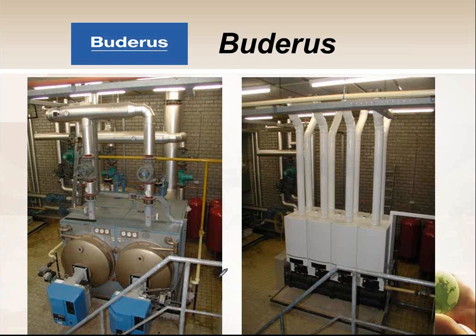Dan's asking if you need to flush these out each year. If so, do you have a supply valve kit? In general, our recommendation, Dan, on all boiler plants, old or new, condensing or non, is that we do not flush the water out of the system.